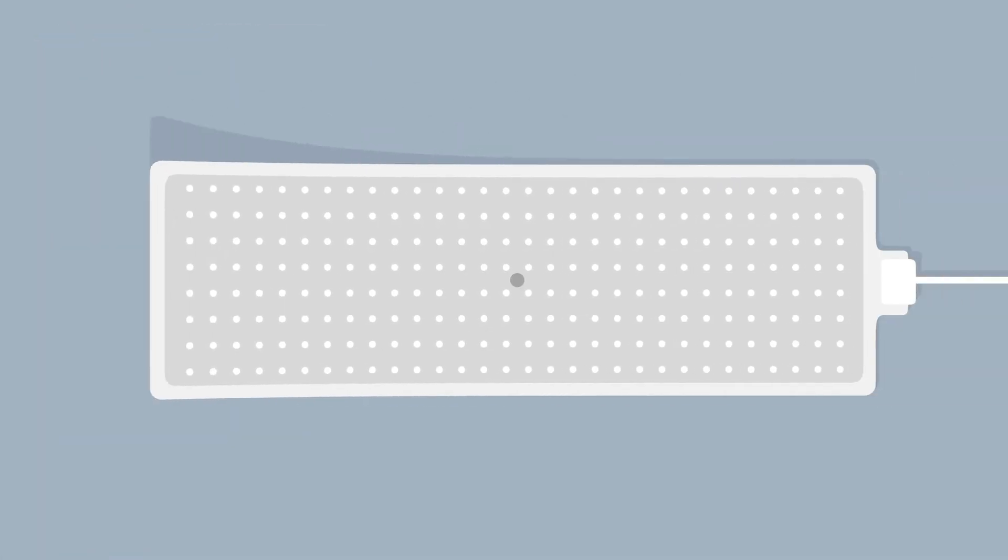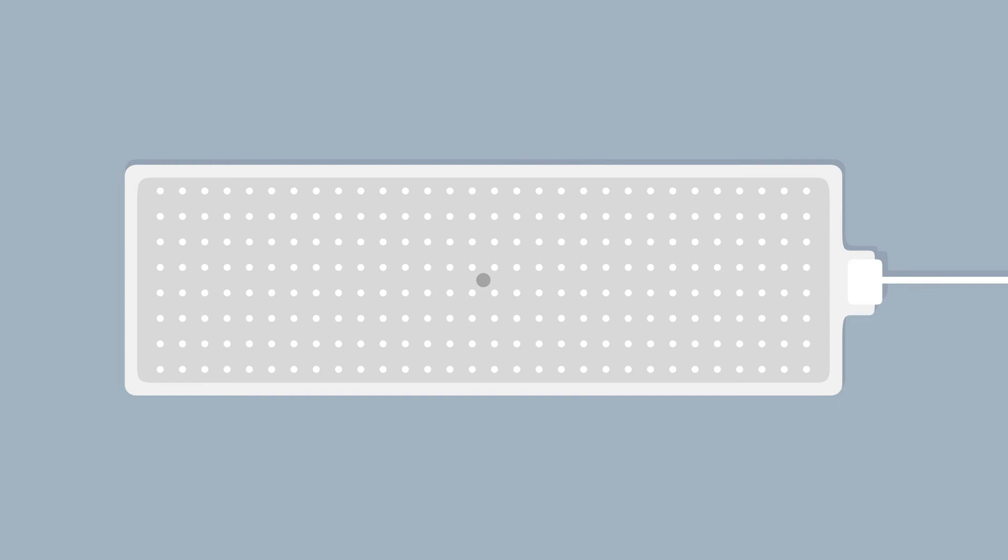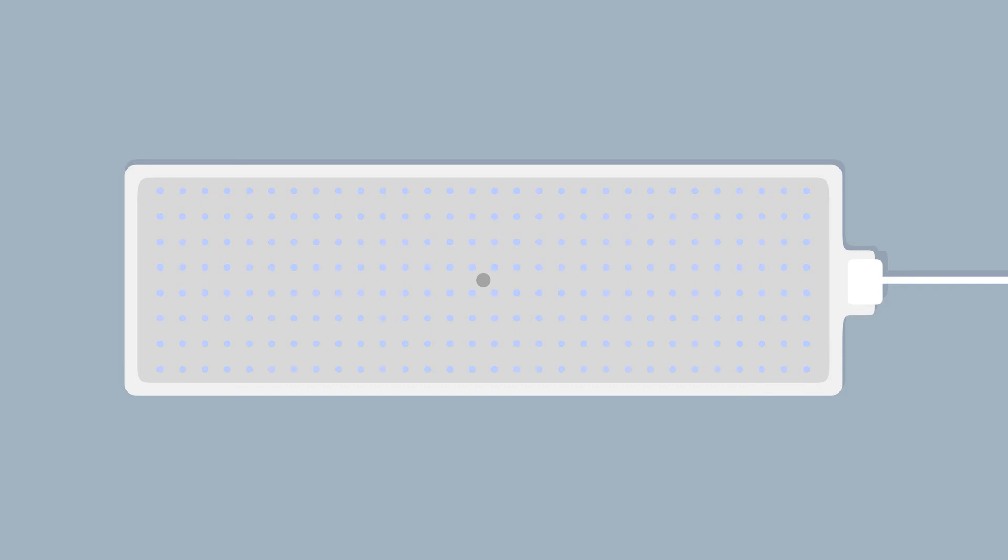The BiliTouch's light pad has a built-in LED module and temperature sensor. This temperature sensor measures temperature in the light pad to protect the patient from the heat of the LED. The illuminated area on the light pad is the lighting area from the built-in LED.